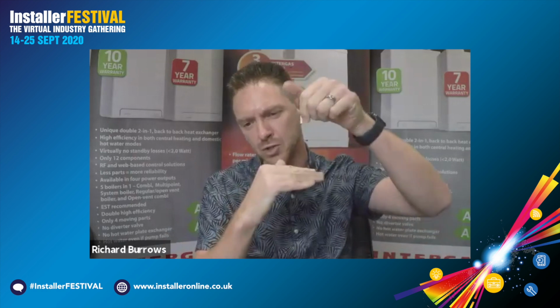So lock shields need really good valve authority. If they're just flat plungers on a valve seat, that's not going to give very good valve authority, because as you close them down to the correct flow rates, you get close but can't quite get close enough, and you just give up. Whereas if you have a tapered valve seat configuration - like a conical seat going into the valve itself - then when you're adjusting it, you can get much better valve authority.